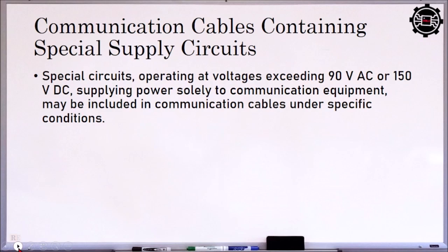So the first condition is cables with conductive sheaths or shield must be effectively grounded. Tapos, each circuit in such cable should be carried on conductors individually enclosed with an effectively grounded shield. So dapat all of those cables have their separate grounding shields, and also they must not be in contact. Walang live parts na makadikit sa kanila. All circuits owned or operated by one party and maintained only by qualified personnel. So yung supply circuit for the communication system and the communication line are owned by the same company. At ang pwede lamang mag-access nun is a qualified personnel which is authorized by the company. Supply circuits terminated at points accessible only by qualified employees.